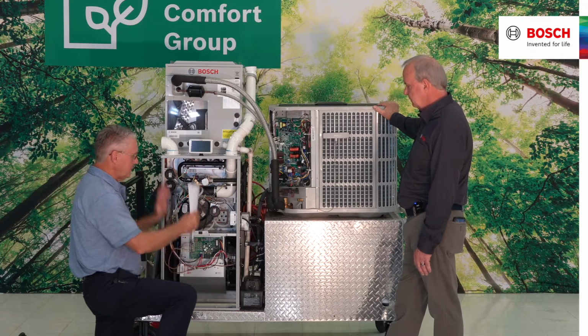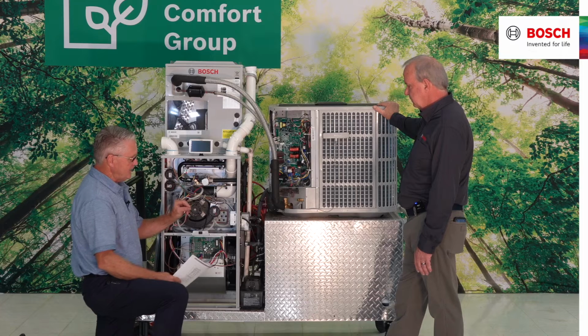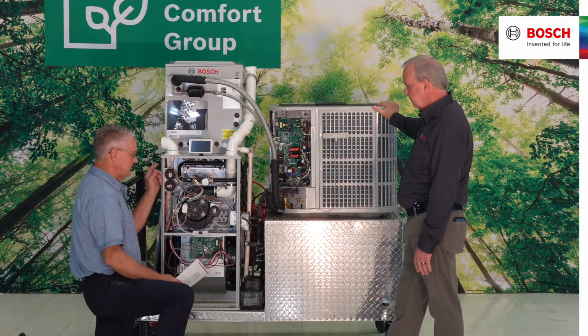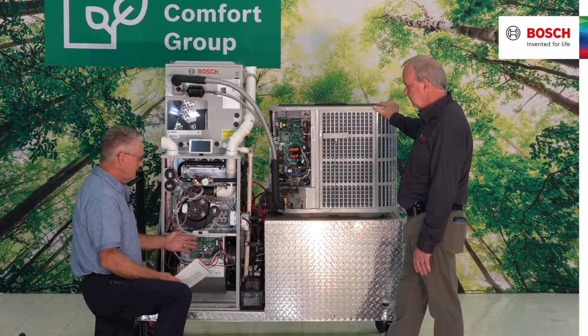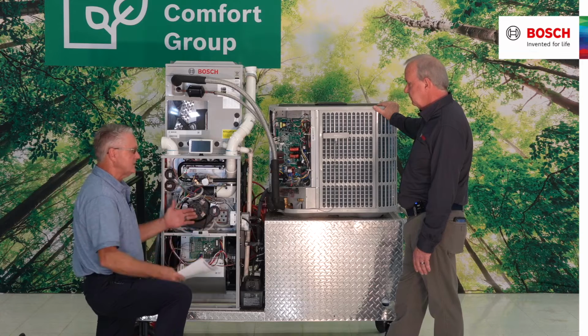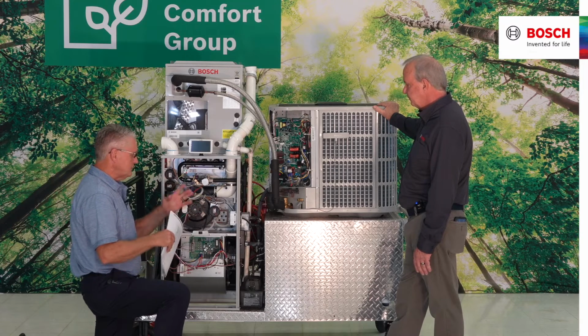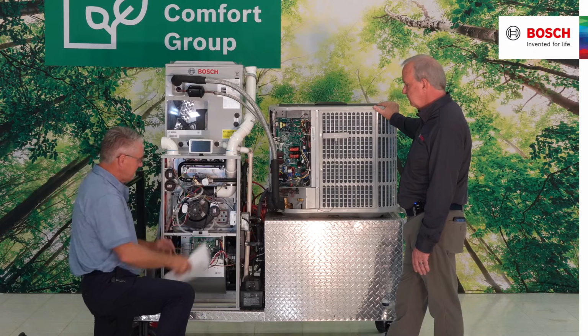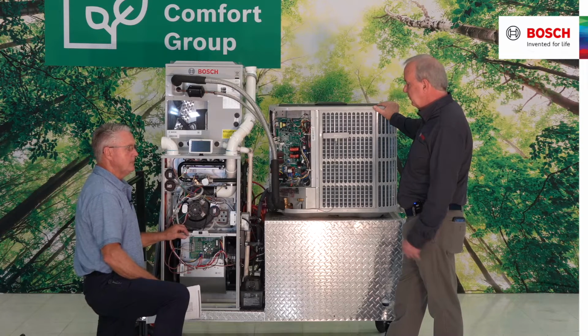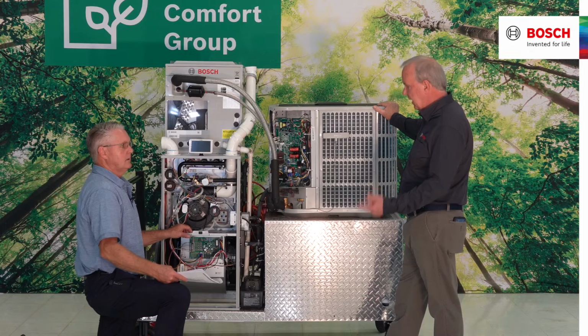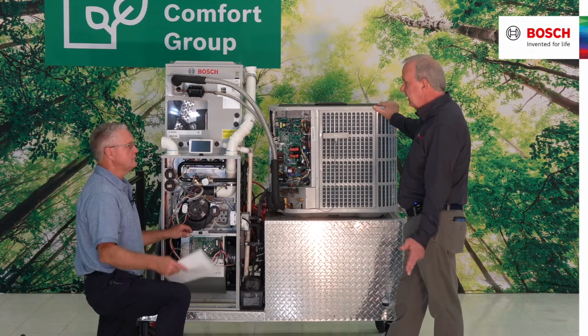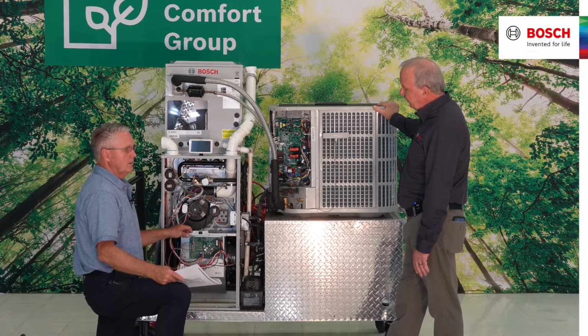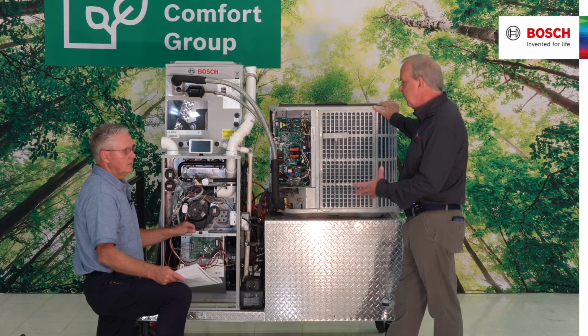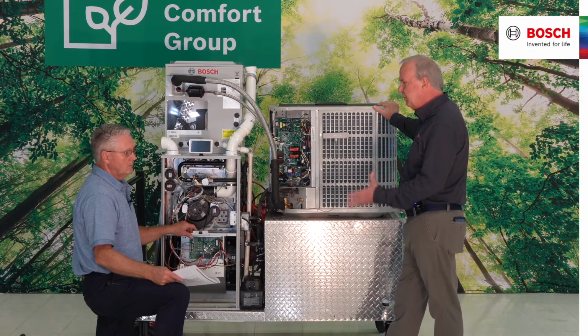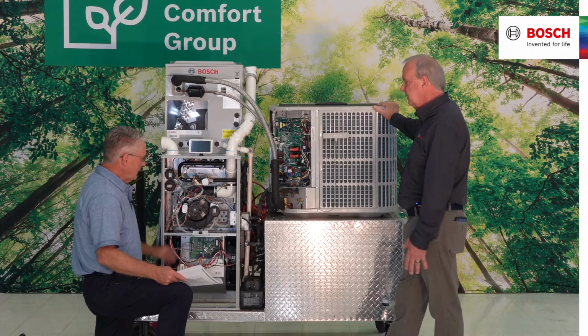I can dial in the fan speed directed to the CFM and my static of my ductwork, basically dialing in somebody's comfort using four speeds out of that five-speed blower motor. So that would be W1, W2 in heat, Y1, Y2 in cooling? Yes, sir, absolutely. Is there a specific CFM where this equipment performs better, or a recommended CFM per ton?